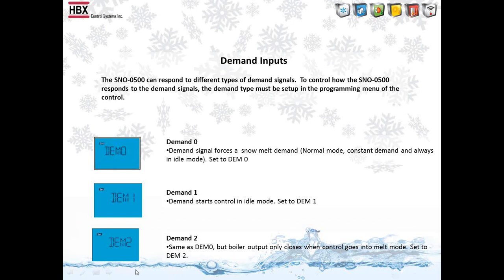DEM2 is basically for BMS systems. So what this allows you to do, it's the same as DEM0, but the output for the boiler demand only turns on when you go into melt mode. So what this allows us to do is talk to BMS systems to basically interface our system to the BMS system. So keep in mind that if we are still controlling any of the pumps or the system temperature or anything like that, you still want to be in DEM1 or DEM0. This is only if the BMS system has full control over the system.